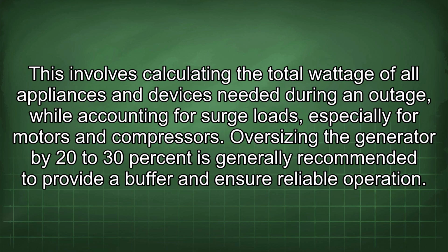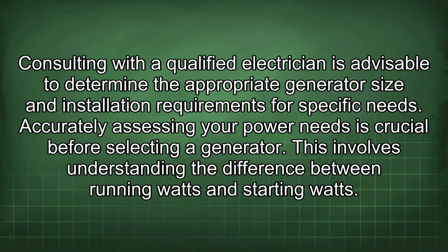This involves calculating the total wattage of all appliances and devices needed during an outage while accounting for surge loads, especially for motors and compressors. Oversizing the generator by 20 to 30% is generally recommended to provide a buffer and ensure reliable operation. Consulting with a qualified electrician is advisable to determine the appropriate generator size and installation requirements for specific needs. Accurately assessing your power needs is crucial before selecting a generator.